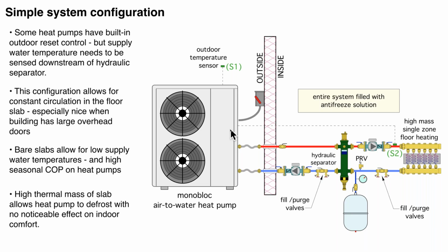They have internal controls that can be set up for outdoor reset. One of the things I would tell you to check when you're looking at these heat pumps is, can they access what I call a system sensor, a sensor that is outside of the heat pump that could be monitoring the temperature at this location. If you can't do that, the other alternative is to use a separate outdoor reset control that can do that and simply turn the heat pump on and off based on that separate outdoor reset control.